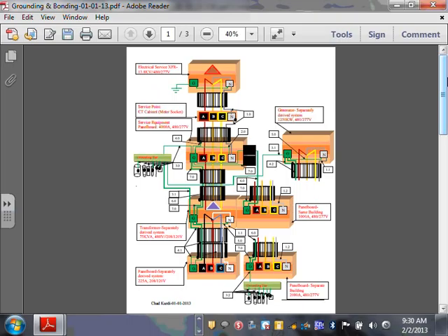If you did a commercial building, typically a big grounding bar will be in the electrical room, where you bring all your grounding electrode system into this bus bar. You don't have to do that, but if you have a bigger system, it's really cool to bring it in. Imagine this bus bar is a collector for all the grounding electrodes in the building. All these little things going down here go to a water pipe, the steel of the building, ground rods, the grounding electrode conductor, a ground ring around the building, and all the approved grounding electrode systems in your building. You can collect them all in one bus bar and bring them into your switchgear. Does that make sense?